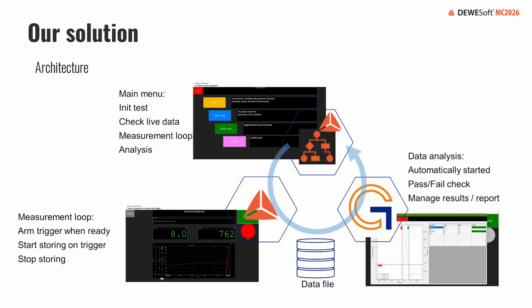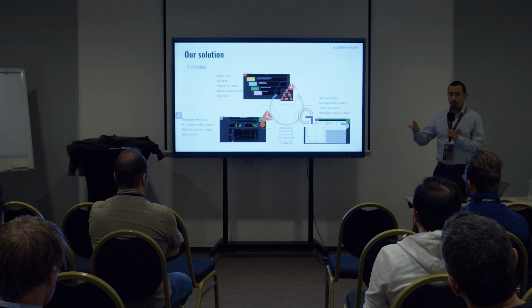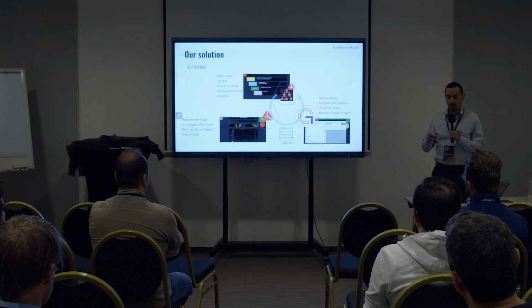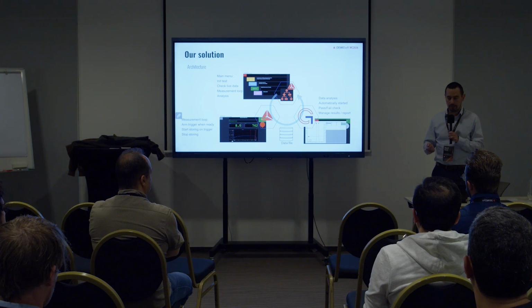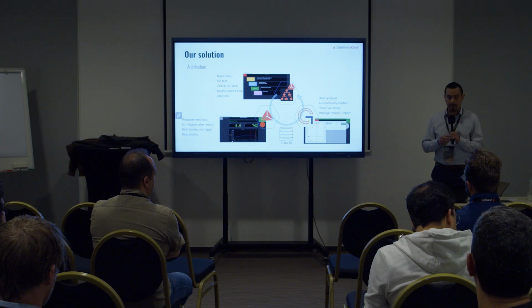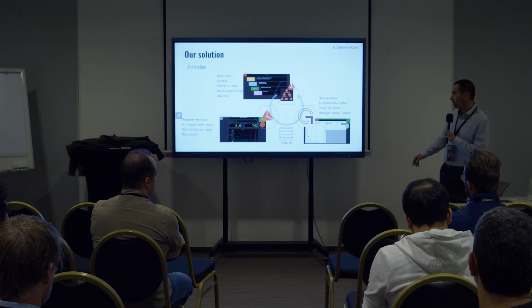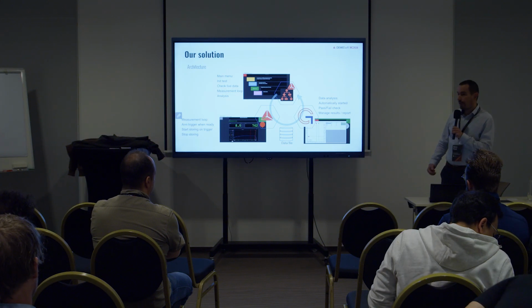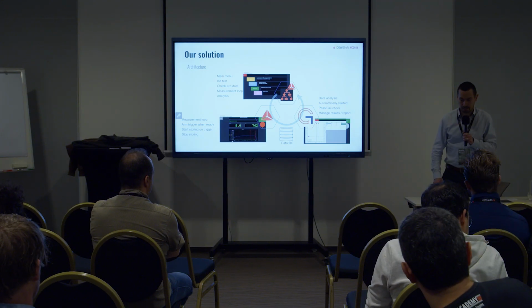So basically, you have a menu in the setup, which is managed by the sequencer. And the menu allows, through just a few buttons, the driver to set some initialization parameters, then to inspect the live data, go to the measurement loop, and to the analysis. When he goes into the measurement loop, he enters another screen with some buttons to store background noise, to start the measurement. Measurements are stored in a data file, and automatically the post-processor provides the results of the measurement.